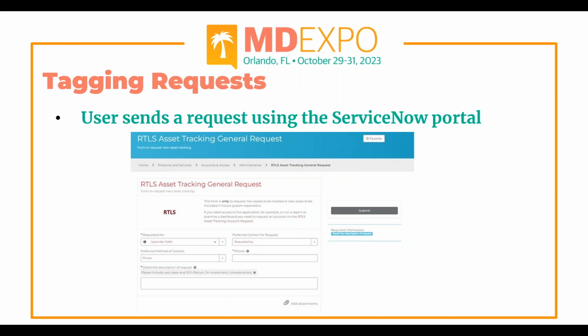So tagging requests: when end users do want to place requests to tag, we do have a ServiceNow portal. We have an electronic form which they can fill out. In this form, typically we want them to identify the name of the device, the quantity of the device, and just let us know where this device is being placed. Because we do have areas at Cedars which do not have RTLS coverage around the campus, or they take it to another building. So it's very important for us to really know, if it does meet the monetary value for tagging, where is this equipment actually going to be used on a day-to-day or operational basis. So once they do send out this request, our clinical engineering team does receive the request, and then we will evaluate whether we can tag this device or not.